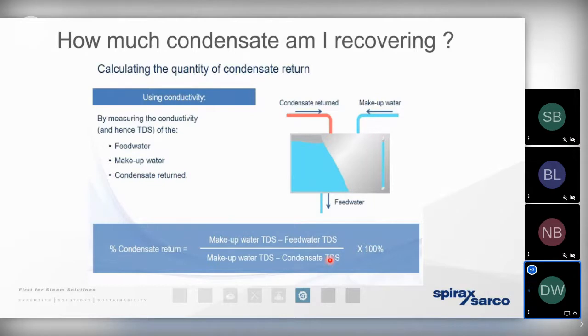They're obliged to take a reading of the total dissolved solids of the condensate that's been returned from the plant, and also the same reading of the water as it leaves the feed tank into the boiler. So we can simply take a ratio of each of those readings to determine a percentage, and that percentage will tell us how much condensate is actually coming back from the plant to the energy center. It gives us a very, very good understanding of how efficiently our steam boiler is working.